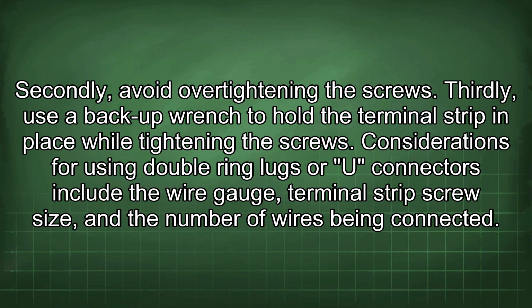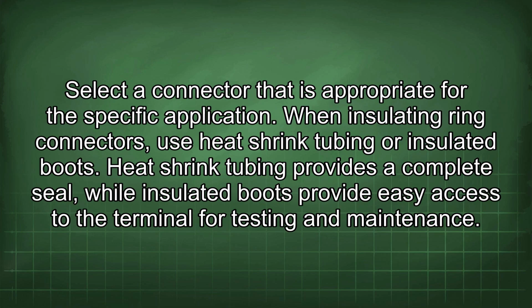Considerations for using double ring lugs or U-connectors include the wire gauge, terminal strip screw size, and the number of wires being connected. Select a connector that is appropriate for the specific application.